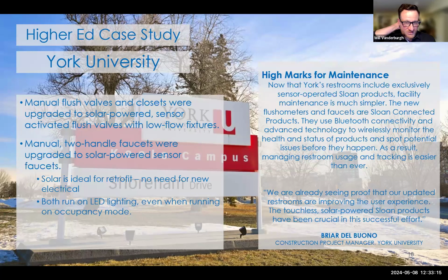In one of the universities I've worked with, they had hardwired flush valves, but that meant that whenever there was maintenance to be done on those flush valves, they had to send a plumber and an electrician to maintain them, because they needed the electrician to work on the electrical side of things and the plumber to work on the plumbing side of things. So as they're now upgrading and retrofitting, they're going to solar power technology so that they only need to send a plumber to that location as opposed to both trades.